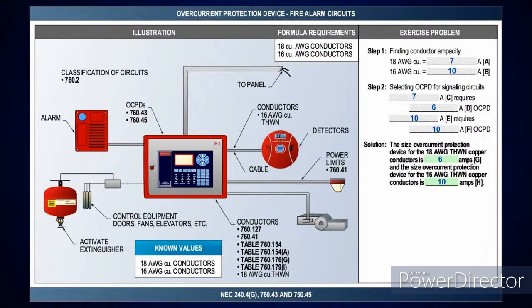Yep. Okay, now this one's very easy. This is just a quick one. You go look at 760.43 where we're dealing with our fire alarm circuits. The information's already given to you. We just put this in, so there's no calculation. When you go over and look at it, it's going to tell you number 18 is good for 7 amps and number 16 is good for 10 amps. Therefore, once you know that, you've got 7 amps, drop down to the next standard size. That's a 6 amp overcurrent protection device. A 10 lines up, so you've got a 10 amp overcurrent protection device.